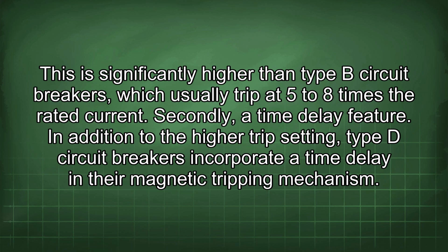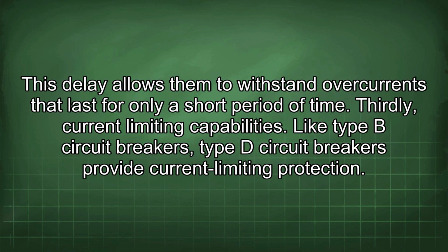Secondly, a time delay feature. In addition to the high trip setting, Type D circuit breakers incorporate a time delay in their magnetic tripping mechanism. This delay allows them to withstand overcurrents that last for only a short period of time.